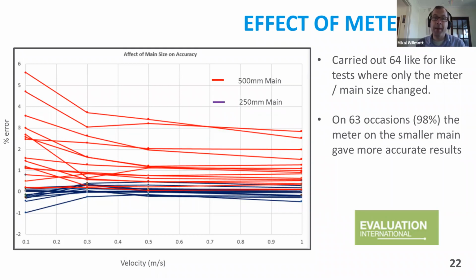They did the same for some electromagnetic meters, tested on a 250 mil rig and then a 500 mil rig. And what we see is basically small is beautiful: we get better results on smaller mains than we do on larger mains. That's quite important when you're trying to work out your uncertainty, or maybe you're deciding where you're going to put a meter. So maybe you've got a borehole and you've got two pipes coming out and they join a big main. Do you want to put 2 meters on the smaller pipes, or do you want to put 1 big meter on the larger main? This suggests that actually you want to put the meters on the smaller mains. Just have a quick look at the velocity as well. You'll see that as velocity increases, uncertainty goes down, or errors go down.